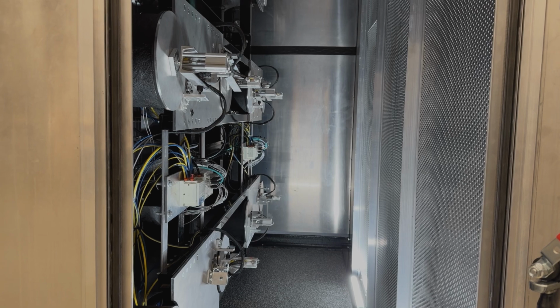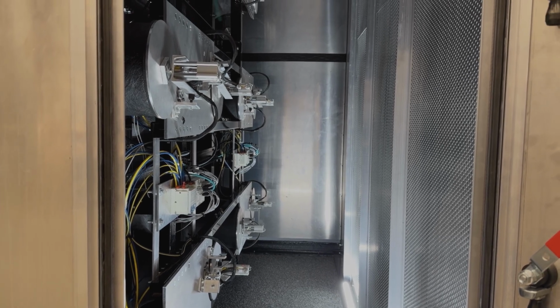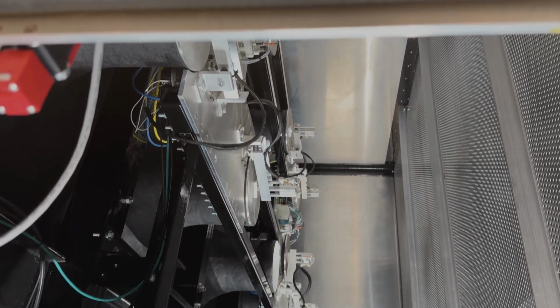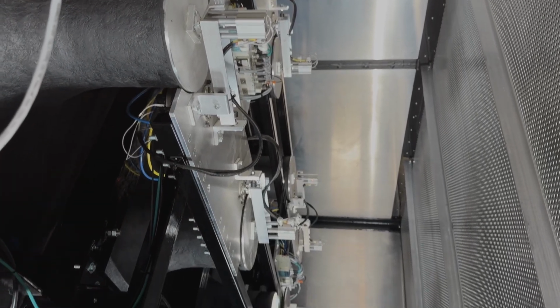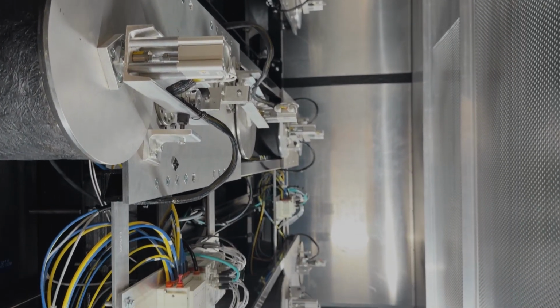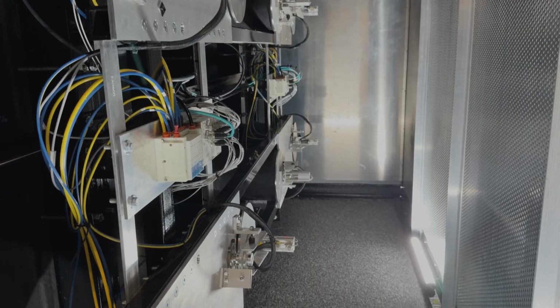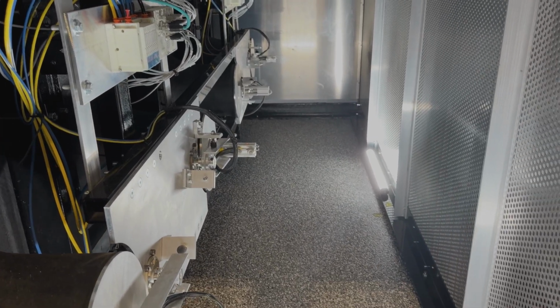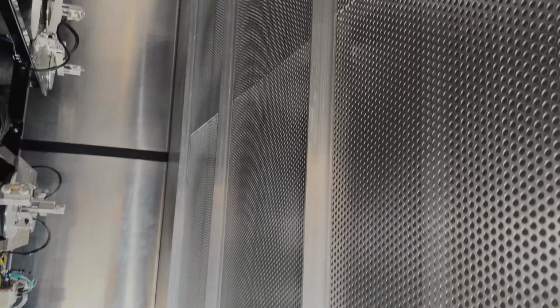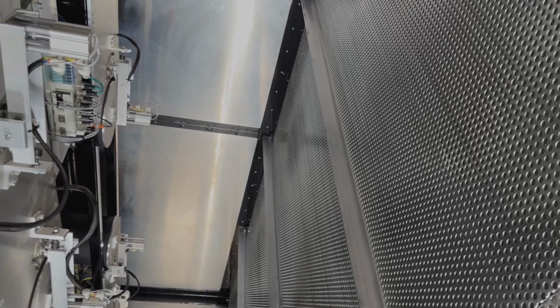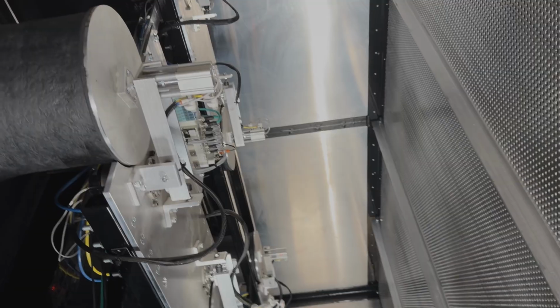So I'm going to ask you a couple questions really quick while we've got this open. So we were talking yesterday, and you were saying that they only fully open or fully close, and that you can only do it in sections. Why is that? Right. So each of the 16 nozzles is either fully open or fully closed. The nozzle profile, we'll see it a little better from the other side, has a specific geometry, and we know through actual physics that the pressure difference from one side of that nozzle to the other, combined with the geometry, tells you exactly how much air is flowing through that nozzle. If we partially closed it, all those assumptions go out the window, and we really don't know what we're measuring anymore. So we either open it or we close it. And you can see one there about to pan across has that open. You can see the white inside of that nozzle. So that one is fully open, and all the rest of them are fully closed at the current time.